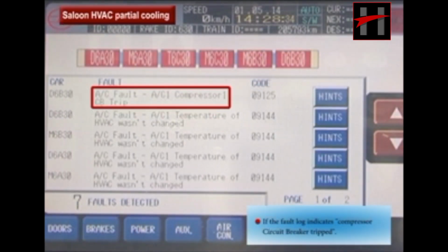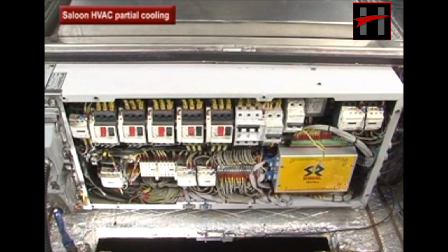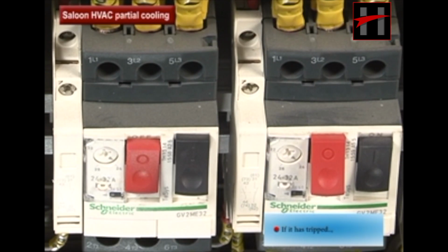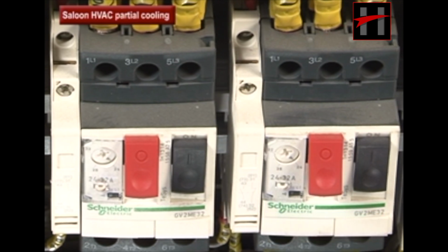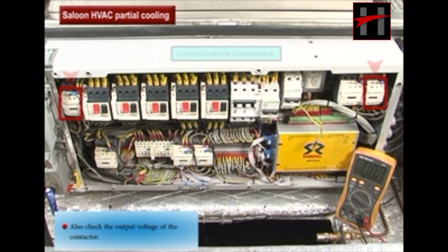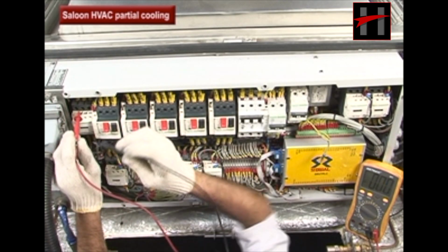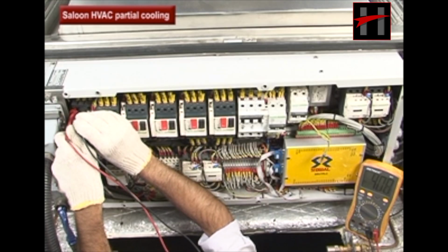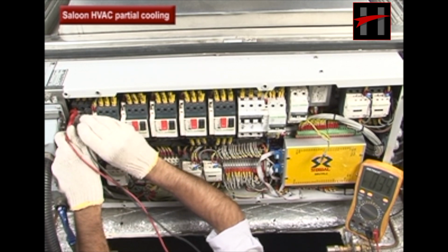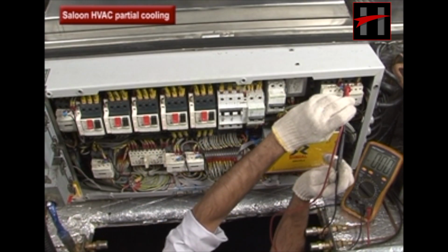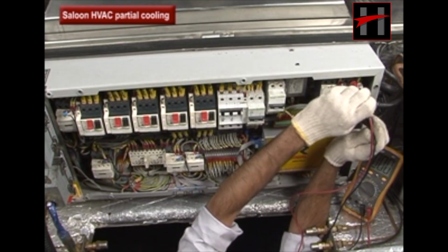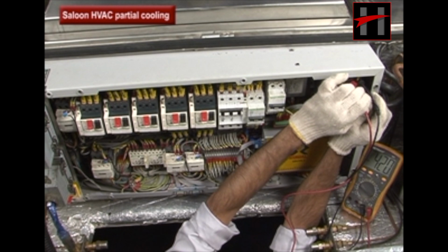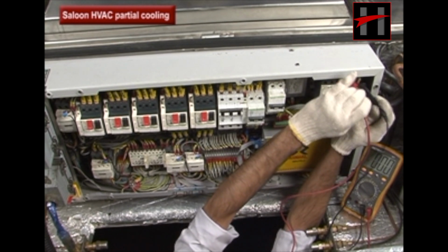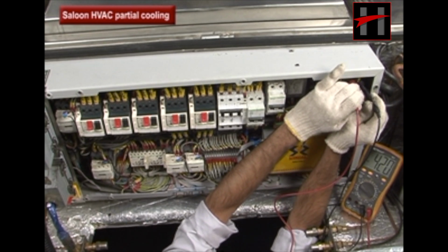If the fault log indicates compressor circuit breaker tripped, check the circuit breaker of the compressor. If it has tripped, reset it. Also check the output voltage of the contactor. If single phase has occurred, the contactor is faulty. Replace the contactor.